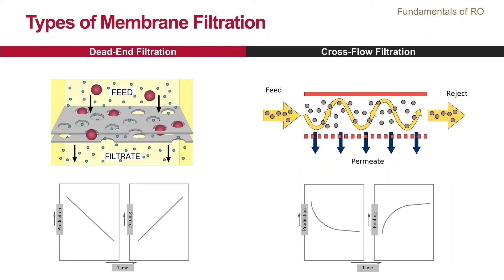In cross-flow filtration, feed water passes tangentially over the membrane surface rather than perpendicular to it. Water and some dissolved solids pass through the membrane, while the majority of dissolved solids and some water do not. Cross-flow helps to minimize fouling or scaling of the RO membrane. In theory, cross-flow is a continuous operation, but in practice it is not always enough to prevent all fouling and scaling — periodically, the membranes need to be taken offline and cleaned.